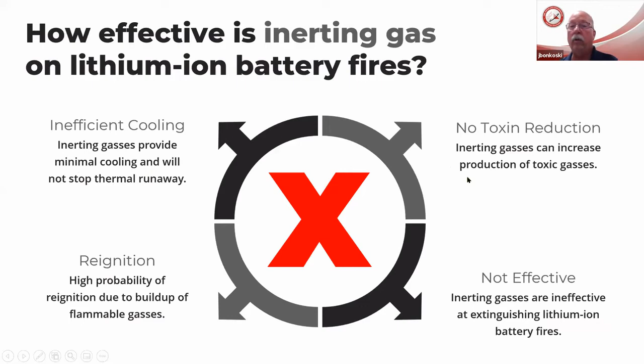Inerting gases. When we look at battery energy storage systems, the Connex boxes or buildings, inerting gases seem to be the way a lot of people tend to go because they figure we can smother the fire. But it doesn't do anything to remove that heat. Once we start getting air and oxygen back into that room, we're going to have a reignition, because those inerting gases do not do anything to cool. It does nothing to reduce the toxins in the soot, the smoke, or the electrolytes. So inerting gases again fall into that ineffective category of agents.